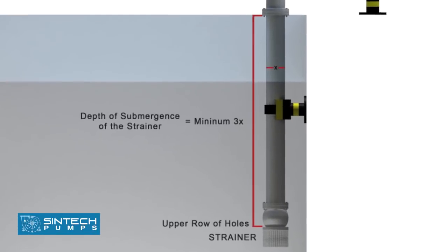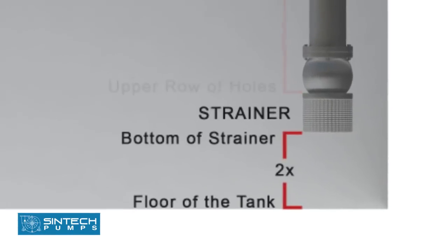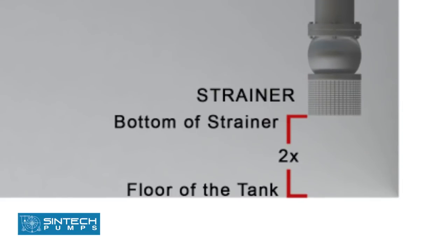The minimum depth of submergence of the strainer should be at least 3 times the pipe diameter measured from upper row of holes of strainer. The distance between the bottom of strainer and the floor of the tank should be considered as 2 times the pipe diameter.